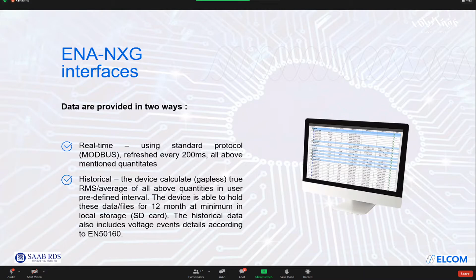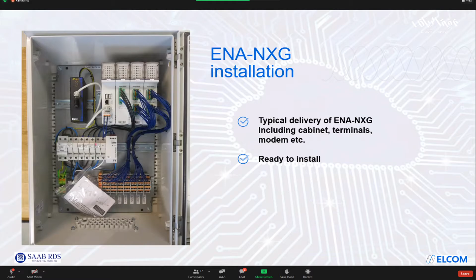This is, for example, how the meter delivered with the cabinet looks like. This is a demonstration from an installation we did in Jordan for the Jordan distribution system operator, IDECO. This meter measures one 3-phase voltage and eight 3-phase currents using external CTs, so it works as a multi-feeder monitor. We also equipped the cabinet with a converter to optical Ethernet, fuses, and a power source, so we can deliver it as a fully equipped cabinet.